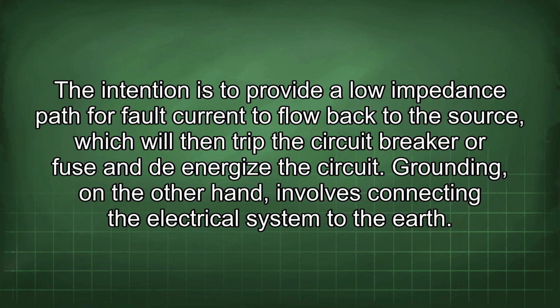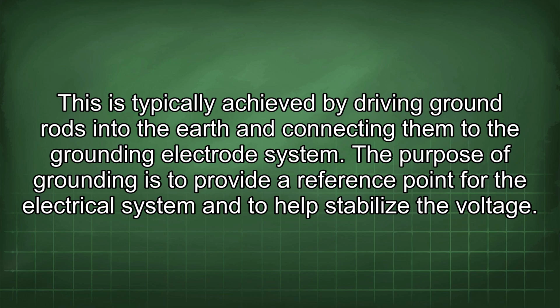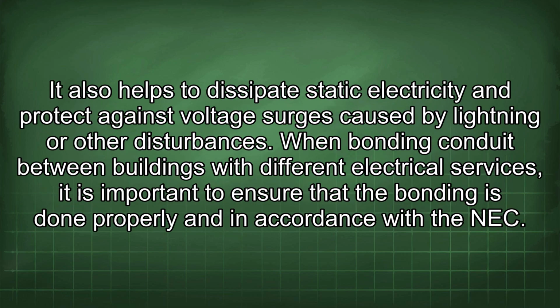The intention is to provide a low impedance path for fault current to flow back to the source, which will then trip the circuit breaker or fuse and de-energize the circuit. Grounding, on the other hand, involves connecting the electrical system to the earth. This is typically achieved by driving ground rods into the earth and connecting them to the grounding electrode system. The purpose of grounding is to provide a reference point for the electrical system and to help stabilize the voltage. It also helps to dissipate static electricity and protect against voltage surges caused by lightning or other disturbances.